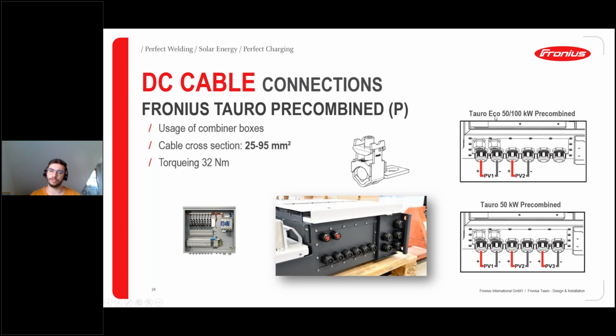On the Fronius Tauro ECO 50 and 100 kilowatt device, we also have 6 cable glands, but we only use 4 of them for 2 string connections. And for the Tauro 50 kW, if we recall correctly, we have 3 MPP trackers. Therefore, we have 3 string connections, and we use all 6 of the cable glands. That's a small difference as well here in the products. And yeah, if we install it, we go through the cable glands. Inside, we install on the V-clamp, and please always make sure to torque correctly. We have a recommended torque here of 32 Newton meters on the DC side.